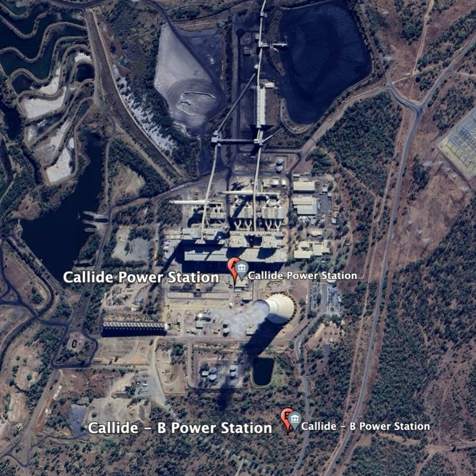At 2:04 p.m., a small number of operators and technicians were cleared to return and re-entered the control room in Callide Unit C4. At approximately 2:05 p.m., a technician managed to restore some power to the control room computers and screens for Unit C4. However, the displayed SCADA information was conflicting. The control room operators were still unclear if the steam valves were open and were still connected and driving the turbine. They were concerned that if they asked PowerLink to disconnect from the grid without the grid to work against, the generator would accelerate into an overspeed condition and tear itself apart.